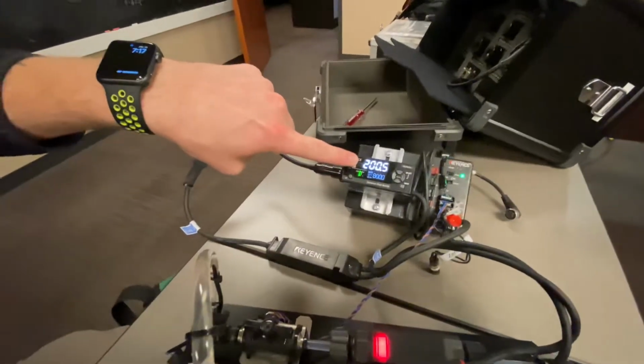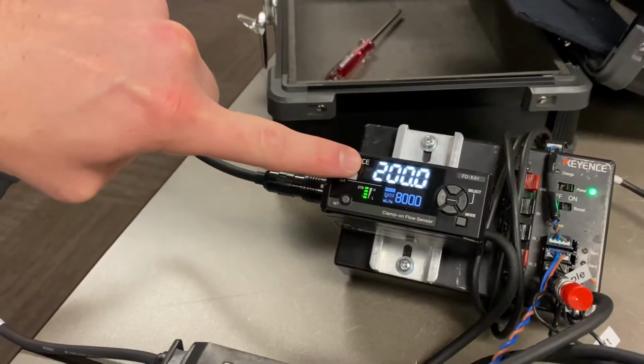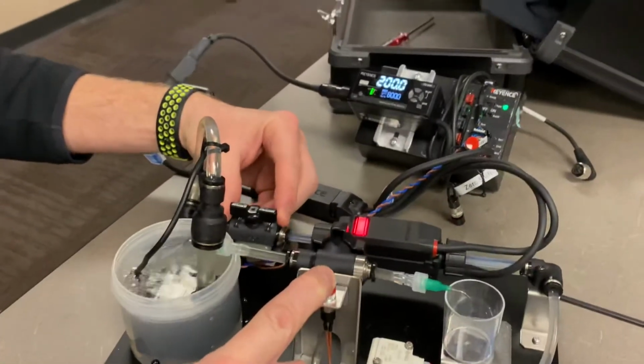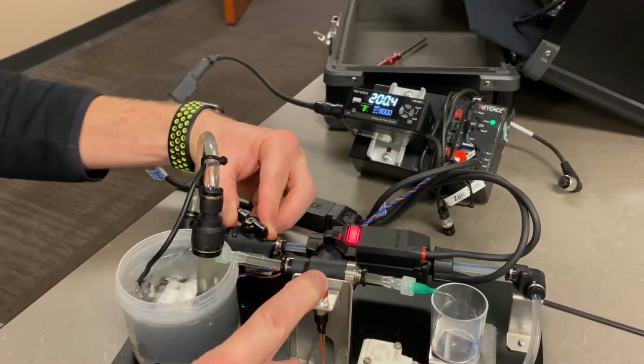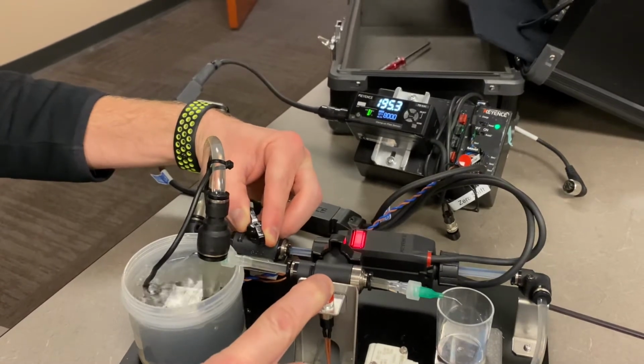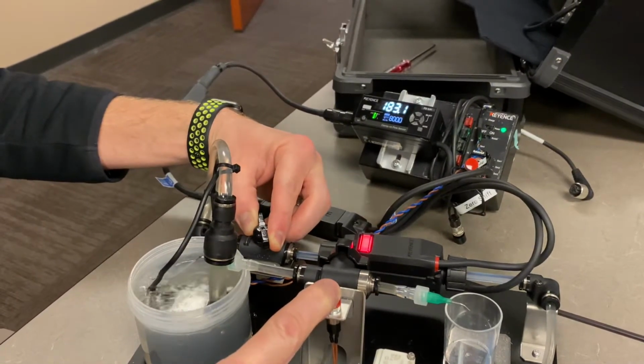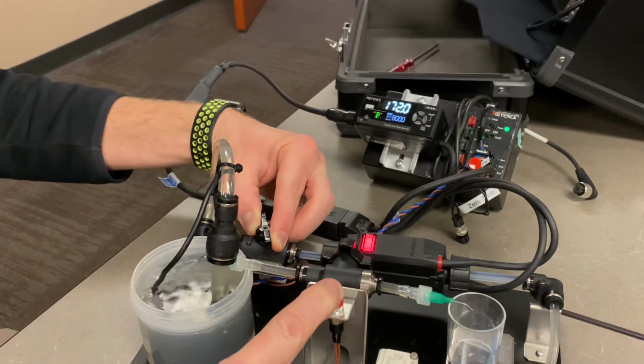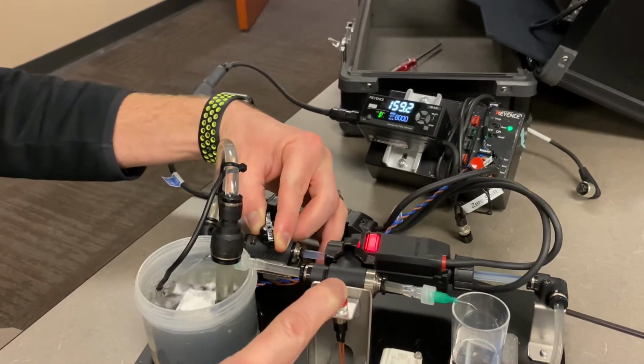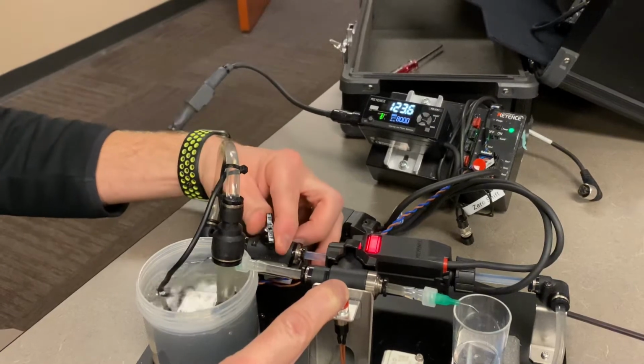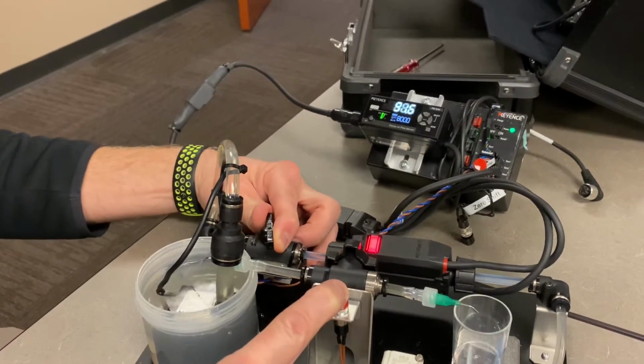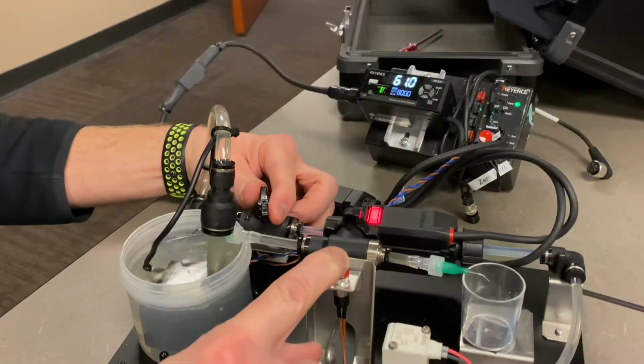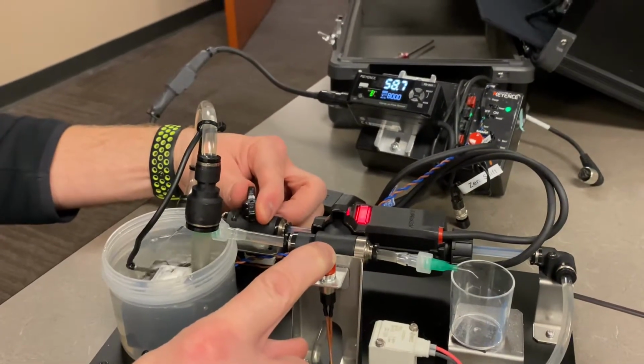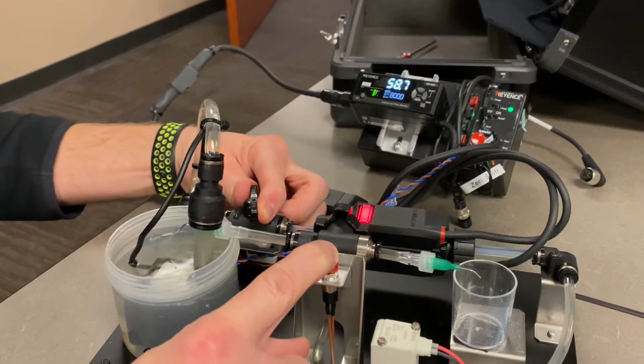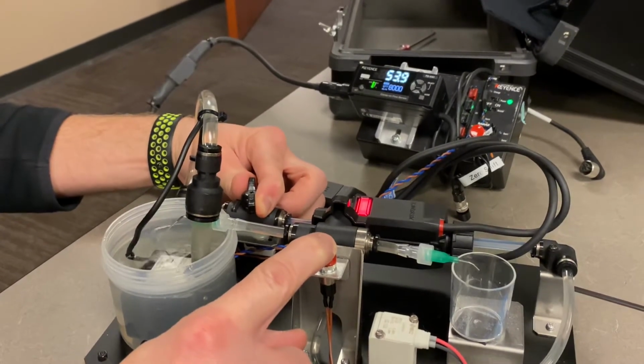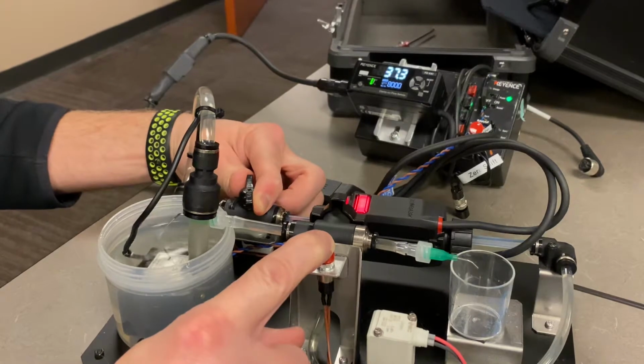As I turn down the flow rate with my little throttle here, pinching the line down, you can see it start dropping. Now I'm at about 170. This thing can get down to very low flow rates, down to about 6 milliliters a minute, and I'll show you that here as we turn it down. Right now we're running at about 58 milliliters a minute, so you can see the flow rate starting to die off a little bit. Now my stream is actually starting to shut down.